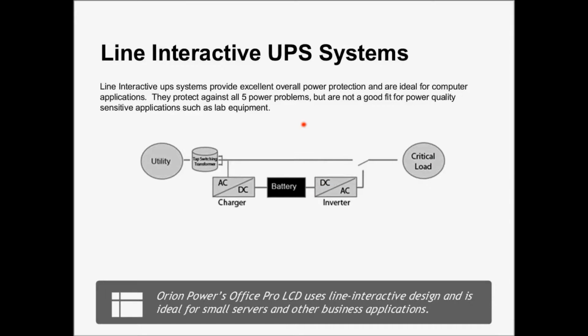The great thing about this is, if you do have a brownout or an overvoltage that's long-term, it can actually use the tap switching transformer to correct for that voltage without using the battery. So that's a line interactive design. Now, one other point I wanted to make is that some of them output a stepped square wave, and some of them are a true sine wave. It just depends on the model, so that's one thing you'd want to check on.